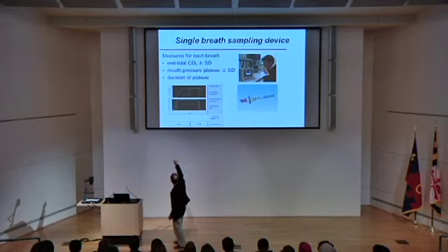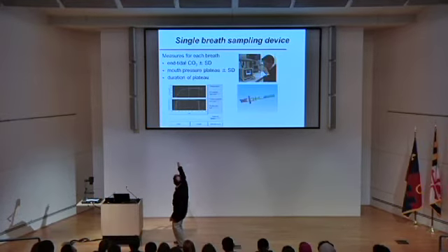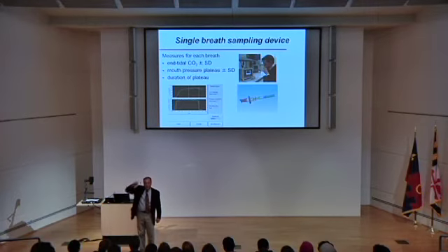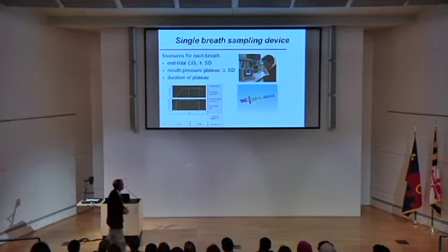And this is actually an instrument that I designed and is built in Italy. You'll have to look here. The pointer doesn't work. This top one is the CO2 profile of a single breath, and the bottom is the mouth pressure. So you ask a person to breathe at a given mouth pressure, and you actually can get a fixed concentration on a single breath, and you can take a sample and analyze it.